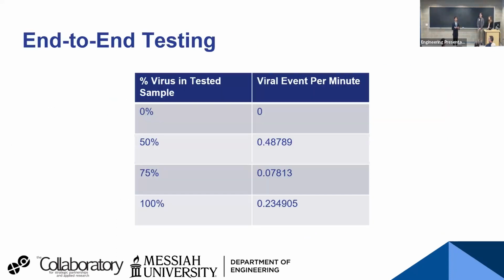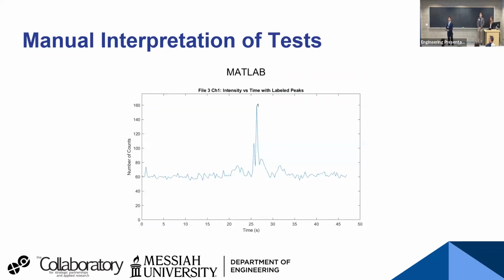With a fully functional optic system, we can then conduct something we call end-to-end testing. That includes preparing the viral sample, then putting it in the optic system and running the tests, and extracting that autocorrelation function data for later plotting. With this, we can determine things like the correlation of a virus in a tested sample, so the concentration of virus in the tested sample. We can create a relationship between that and how many viral events or fluorescent events there are per minute. But the most important thing is the data we're getting out of this end-to-end testing for further research.